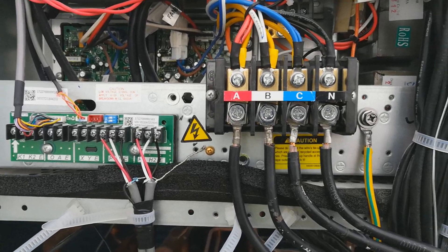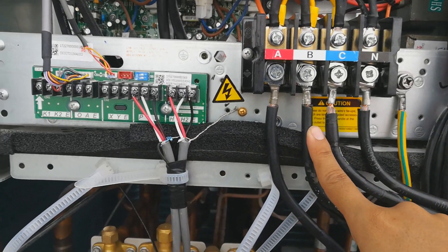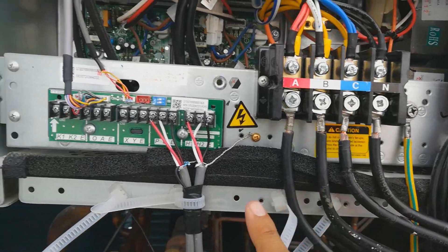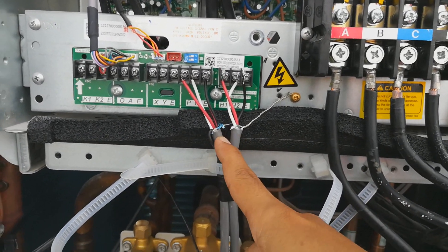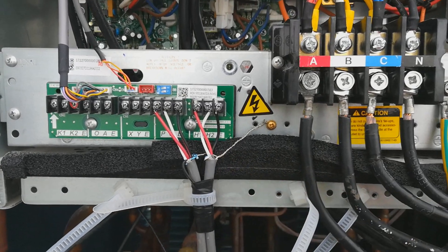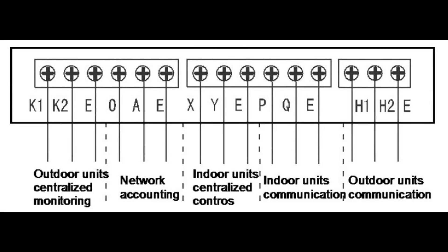Here is the connection of the power supply: A, B, C and N. A, B, C is the phase and N is the neutral. PQE is the indoor unit communication, H1 H2E is the outdoor unit communication. K1 K2E is the outdoor unit central line monitoring, OAE is the network, XYE is the indoor unit centralized control, and PQE is indoor unit communication.